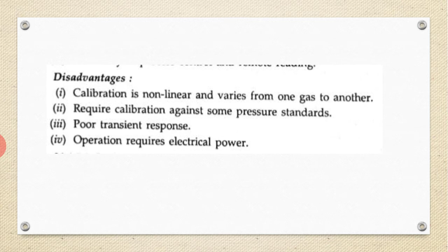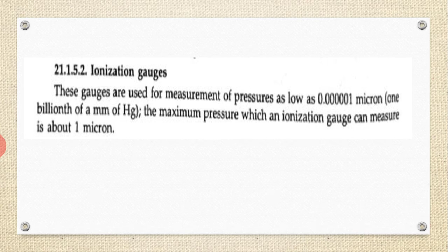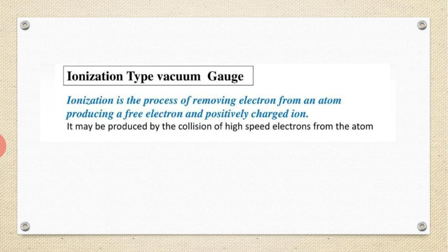Next one is the ionization gauges. These gauges are used for measurement of pressure as low as 0.000001 micron, so one billionth of a mm of Hg. That means you are going to measure very low pressure. The maximum pressure an ionization gauge can measure is about 1 micron. In this ionization type vacuum gauge, the basic process involved is ionization. Ionization is the process of removing an electron from an atom, producing a free electron and a positively charged ion. It may be produced by the collision of high speed electrons with the atom.